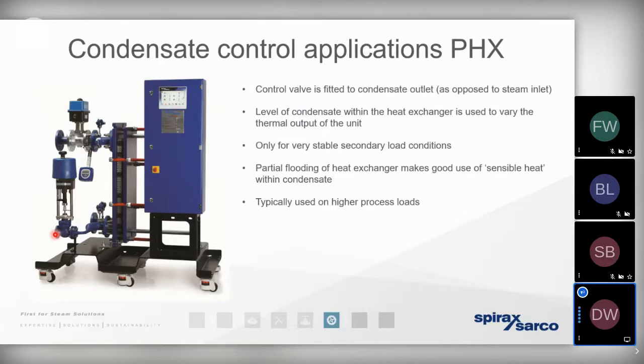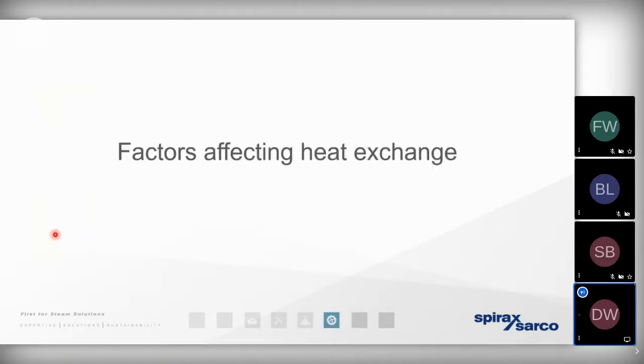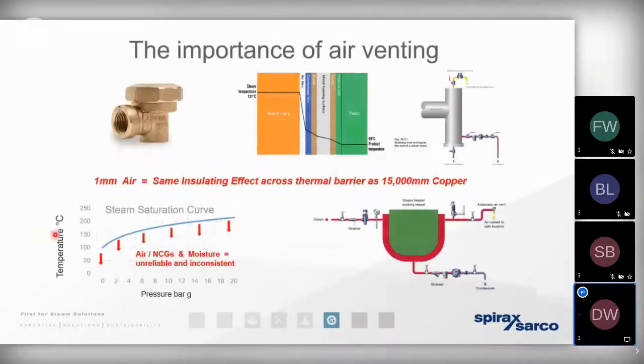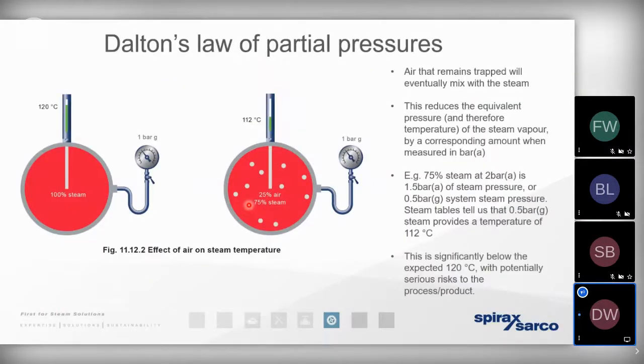So there are a number of factors that can also affect the rate of heat exchange. We've mentioned previously the presence of air. That insulating film of air can be the greatest inhibitor to heat transfer. And it also means that we can no longer rely on that pressure to temperature relationship. And that's really got its basis in understanding Dalton's law of partial pressures. Basically, any air that is present entrained within the steam means the steam will be supplied to the heat exchanger at the expected pressure, but it's simply going to have a lower temperature in it.